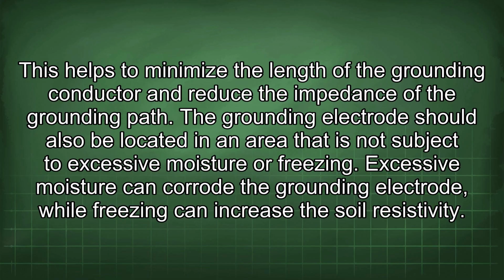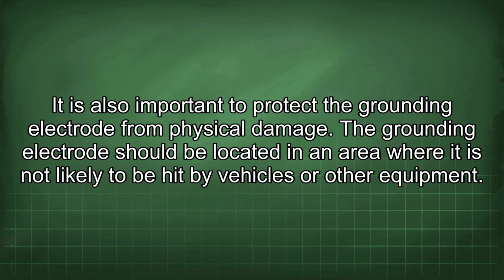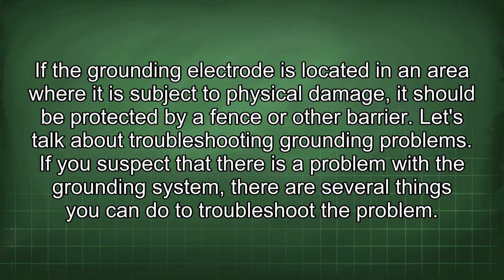The grounding electrode should also be located in an area that is not subject to excessive moisture or freezing. Excessive moisture can corrode the grounding electrode, while freezing can increase the soil resistivity. It is also important to protect the grounding electrode from physical damage. The grounding electrode should be located in an area where it is not likely to be hit by vehicles or other equipment. If the grounding electrode is located in an area where it is subject to physical damage, it should be protected by a fence or other barrier.